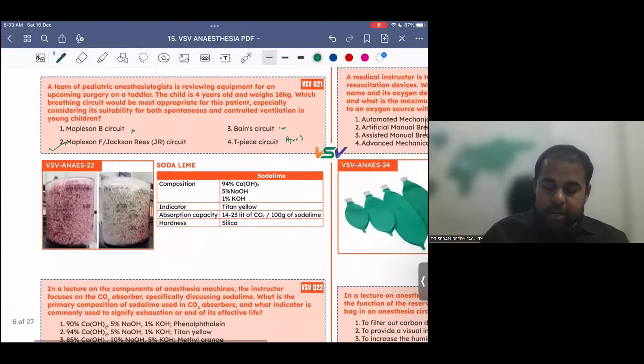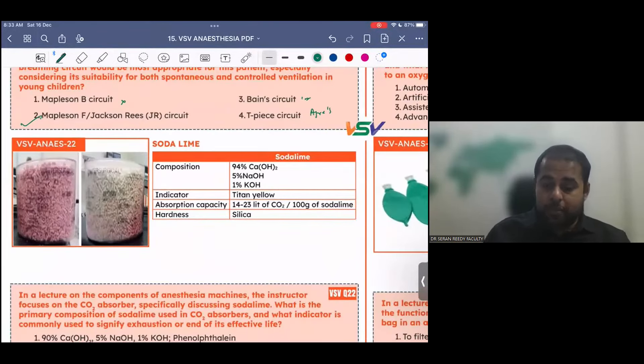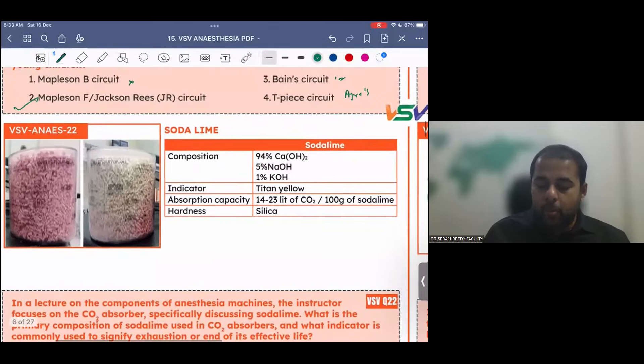Then coming to another important thing. This is carbon dioxide absorber. This is soda lime. Soda lime, there are a few things. Soda lime, barium lime, and AMSOB. But remember, soda lime is the most common thing which we use. The composition is 94% calcium hydroxide, 5% sodium hydroxide, and 1% potassium hydroxide. The color indicator, once it is exhausted, the color indicator is Titan yellow. Remember this, Titan yellow. And absorption capacity, it absorbs 14 to 23 liters of carbon dioxide per 100 grams of soda lime. And hardness, this is hard with the presence of silica in that.